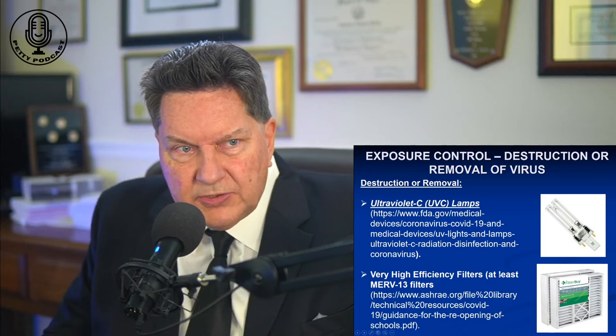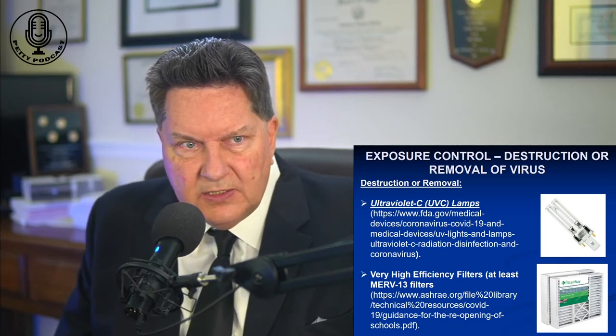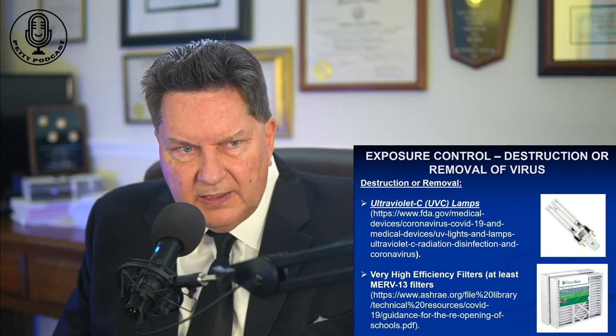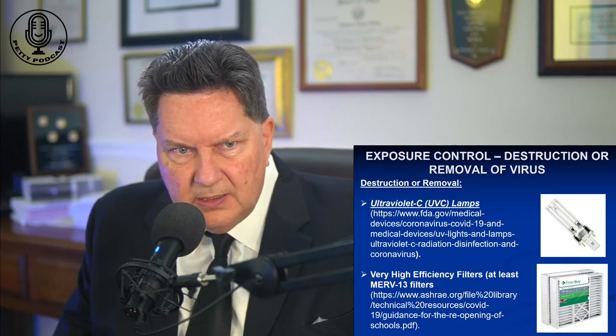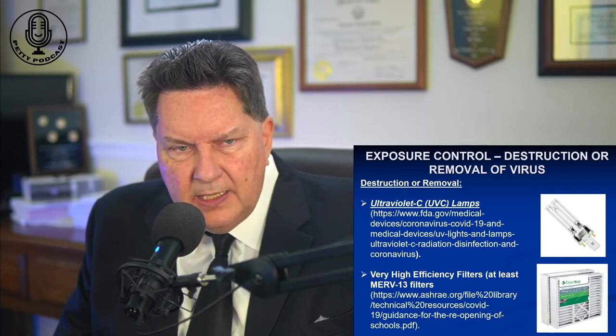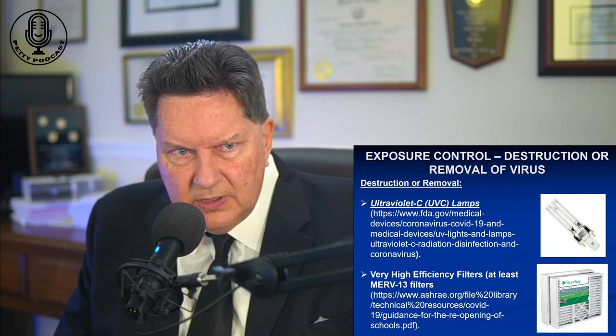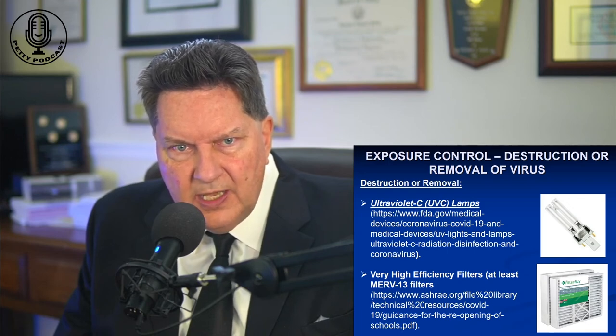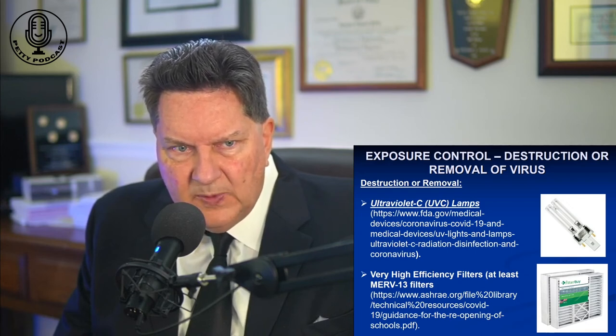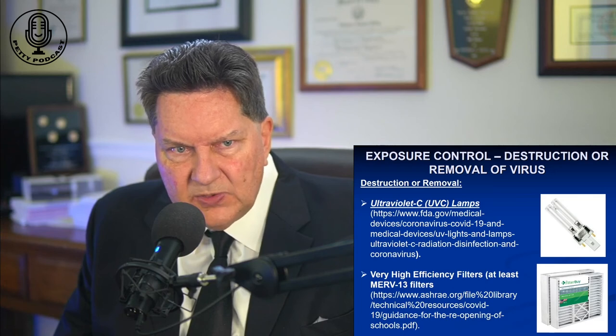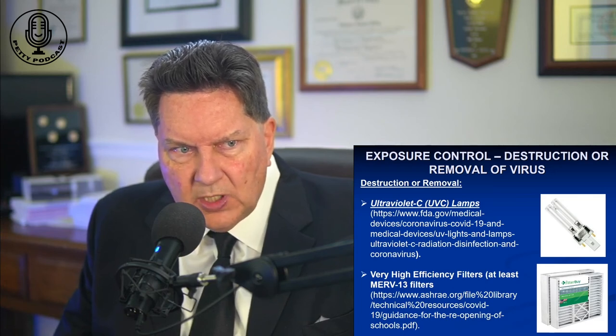The third technology I want to mention is ultraviolet C, or UVC, lamps. Ultraviolet refers to short wavelengths beyond visible light. These UV tubes can be put into your furnace system and they will destroy COVID. The only issue with them, from my experience, is that they do burn out from time to time. You have to check them periodically to make sure they're still working.